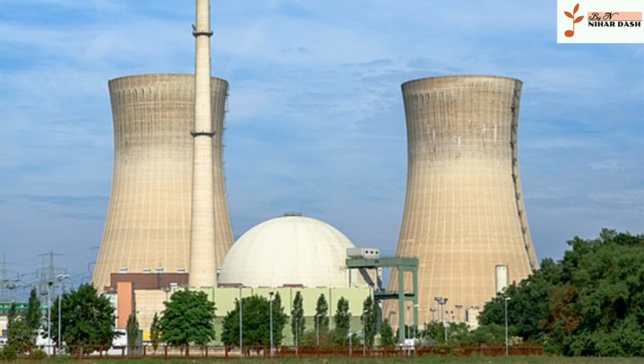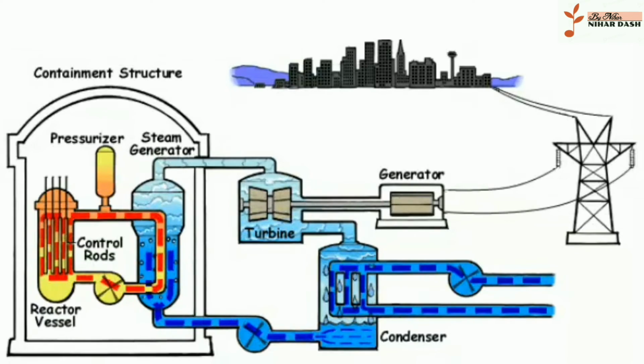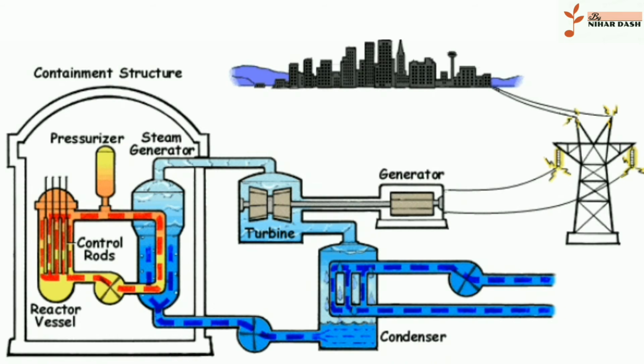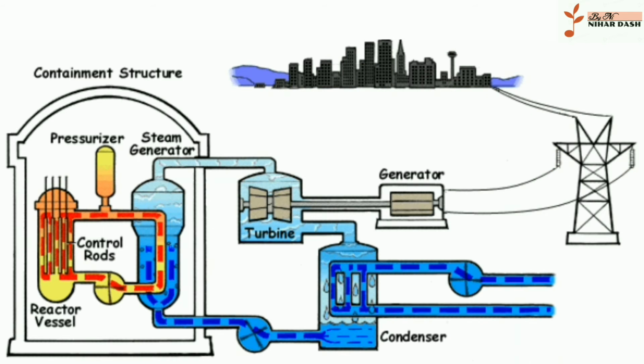To detect a leak in the steam generator, and thus the passage of radioactive water, at an early stage, an activity meter is mounted to track the outlet steam of the steam generator. In contrast, boiling water reactors pass radioactive water through the steam turbine, so the turbine is kept as part of the radiologically controlled area of the nuclear power station. The electric generator converts mechanical power supplied by the turbine into electrical power.